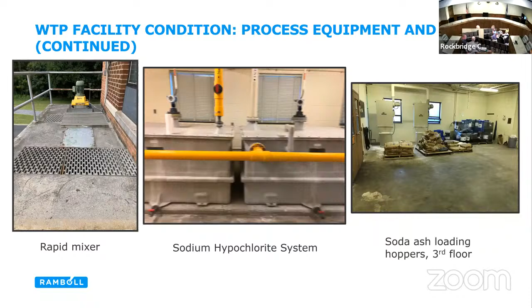From a water treatment plant operation standpoint, the HVAC on the 3rd floor is not there to provide AC and comfort for the humans. That's to prevent corrosion, like you see in the picture. That's to get adequate ventilation and airflow through the 3rd floor. That is typical. That is expected at most facilities, at all facilities. So fluoride and sodium hypochlorite, chlorine, strong bleach, both of those chemicals are highly corrosive and dangerous to the staff. So in any standards after the 1970s, they would have had an adequate ventilation system to keep that air moving and air turnover, so that you didn't have issues and safety concerns with the staff.